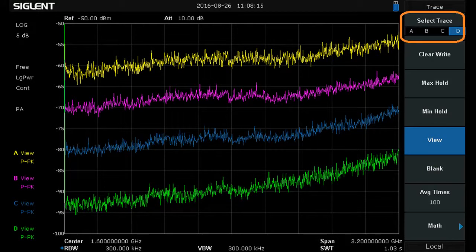The instrument also features the ability to show up to four traces simultaneously. This is four versus the three that is available in many other spectrum analyzers. Having the ability to view four traces simultaneously and being able to configure them each separately allows you to compare more of the traces that you've collected using different setups for the instrumentation or any particular parameters that you may have adjusted while performing data collection. It can be helpful when you're troubleshooting multiple scenarios or different measurement environments.